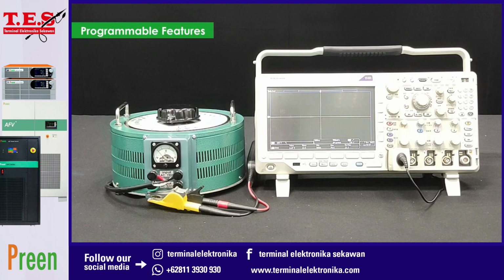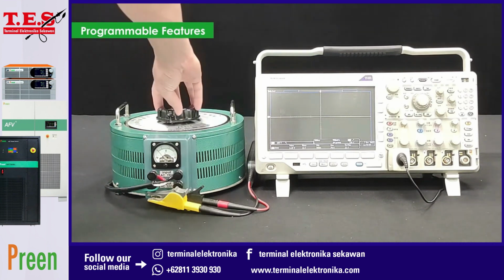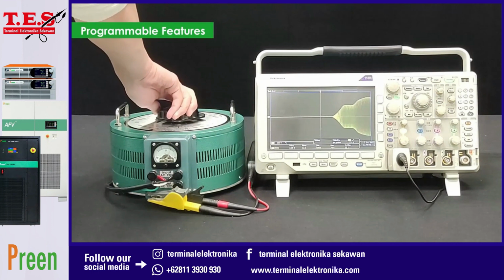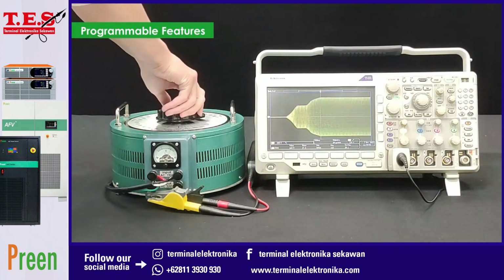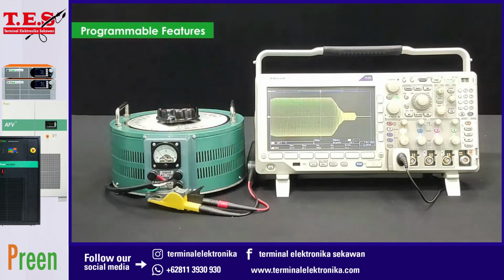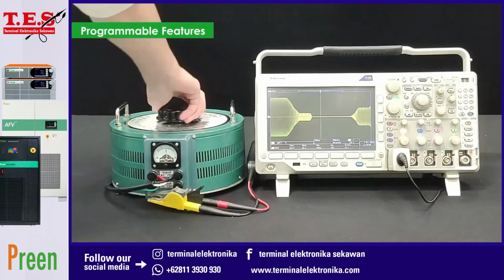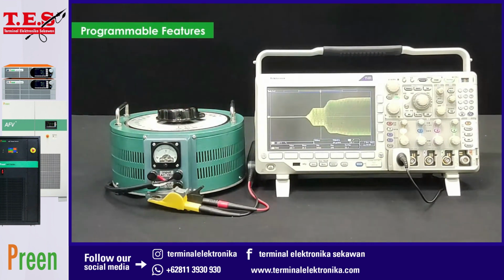Lastly, let's compare programmable features by simulating the short interruption test. The voltage of the variable transformer is 220 volts. As you can see, it is hard to conduct a 2-second short interruption because it is much slower to adjust the voltage by turning the knob. The results could be inaccurate due to slow response time.